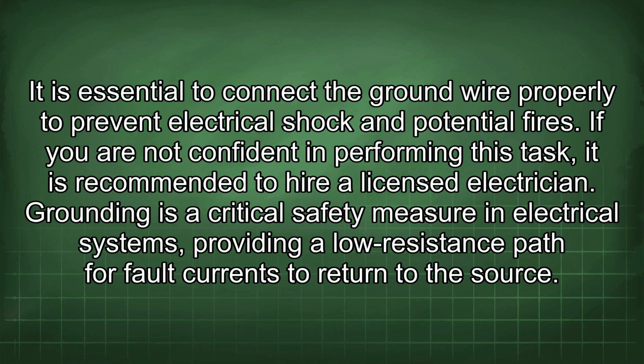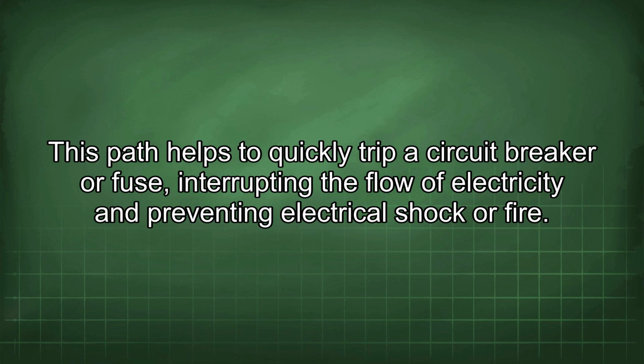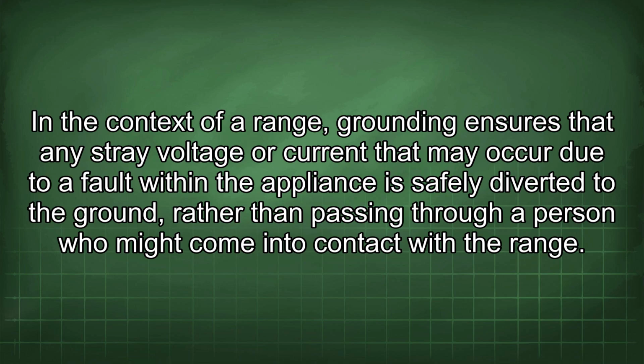Grounding is a critical safety measure in electrical systems, providing a low resistance path for fault currents to return to the source. This path helps to quickly trip a circuit breaker or fuse, interrupting the flow of electricity and preventing electrical shock or fire. In the context of a range, grounding ensures that any stray voltage or current that may occur due to a fault within the appliance is safely diverted to the ground, rather than passing through a person who might come into contact with the range.